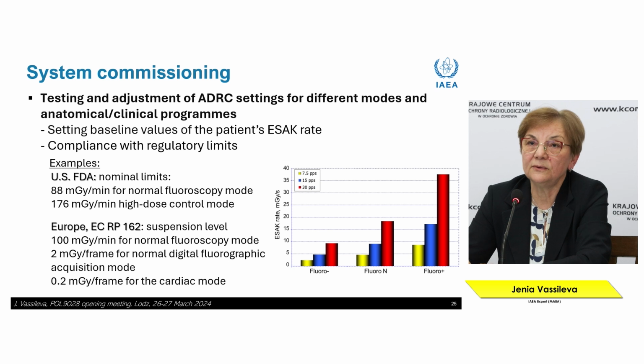For example, in Europe, the European Commission, in a quite old document, Radiation Protection Series 162, proposed a suspension level of 100 milligray per minute for normal fluoroscopy mode, and also different numbers for radiography modes, for cardiac mode, for example, 0.2 milligray per frame.